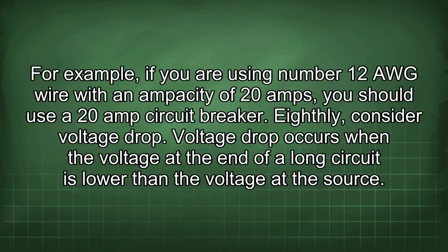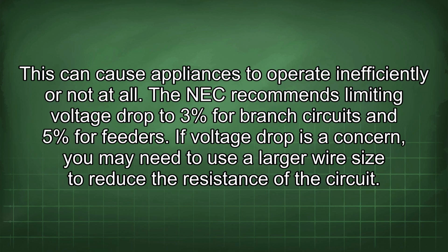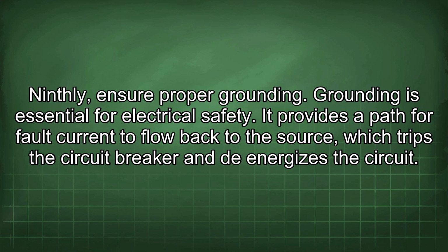Voltage drop occurs when the voltage at the end of a long circuit is lower than the voltage at the source. This can cause appliances to operate inefficiently or not at all. The NEC recommends limiting voltage drop to 3% for branch circuits and 5% for feeders. If voltage drop is a concern, you may need to use a larger wire size to reduce the resistance of the circuit. Ninthly, ensure proper grounding.